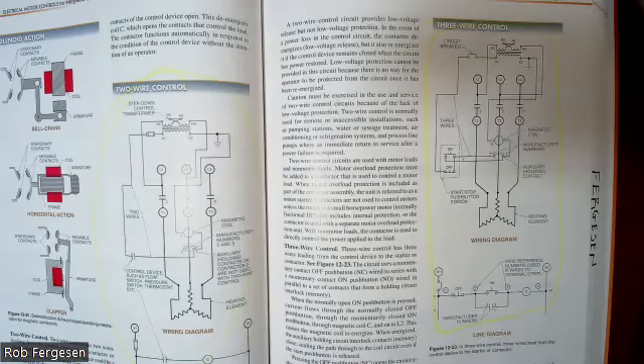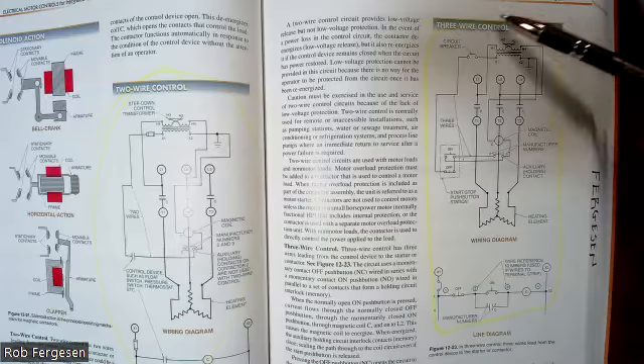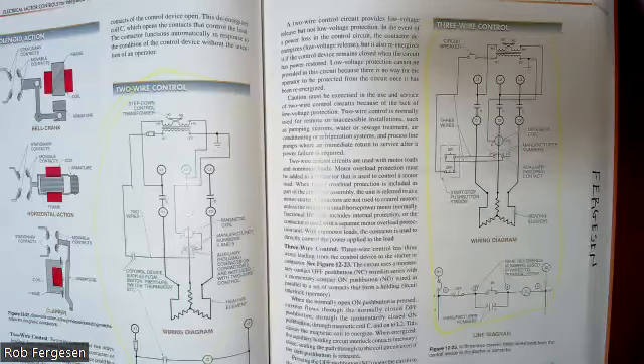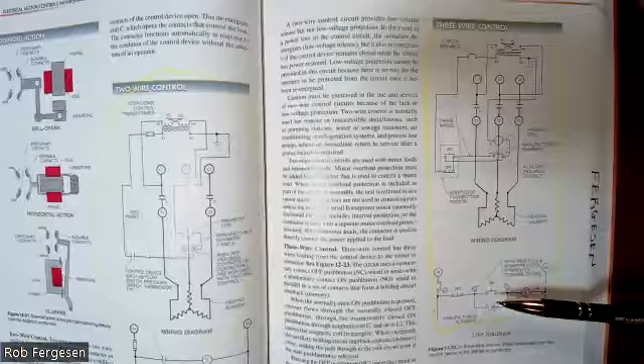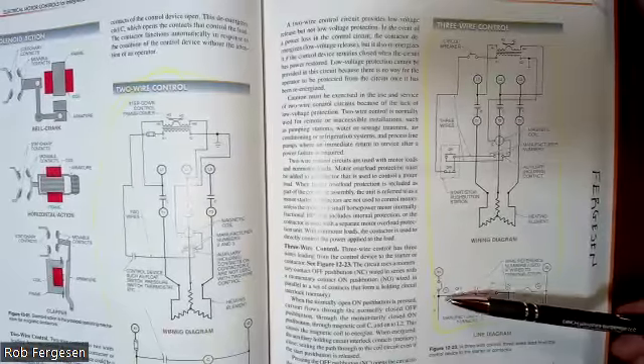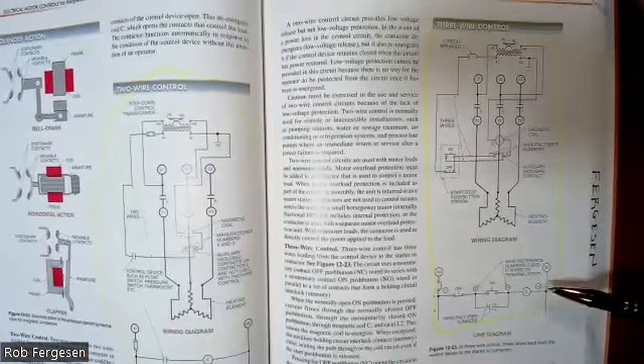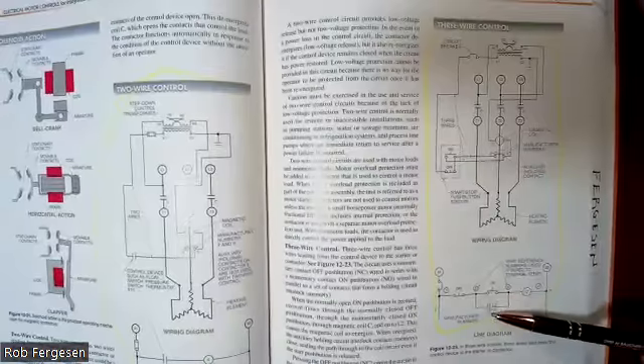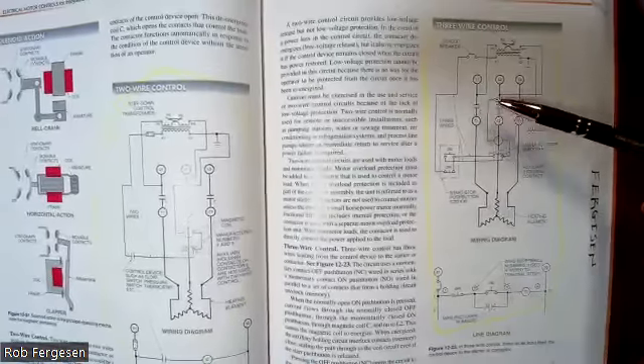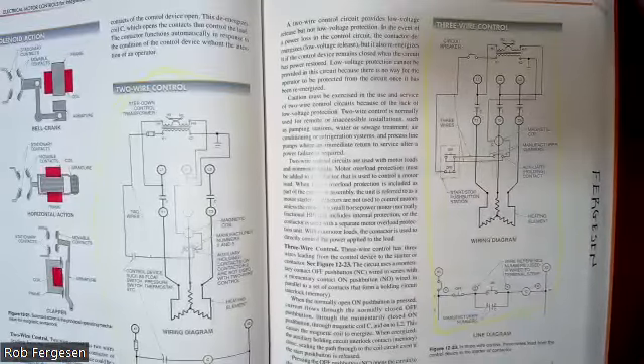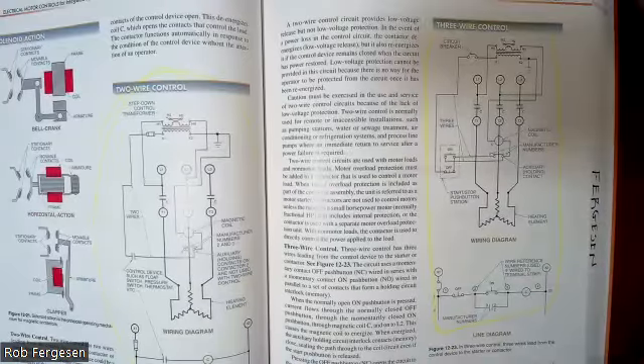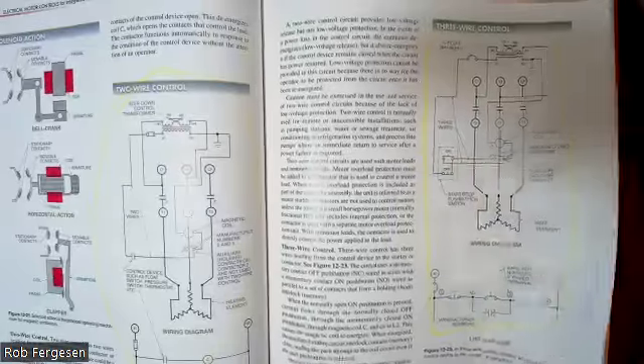That is a typical electromechanical latching circuit. This is probably the single most important circuit in this particular course. Because when you want to turn it off, you just press the off button. That opens up the power, turns off this coil, that opens up this auxiliary contact, opens up all of these 3 primary contacts that lead the 3-phase power into the heating element or the motor, and then it's turned off and stays off. So this is a very typical wiring diagram. I just want to emphasize that.